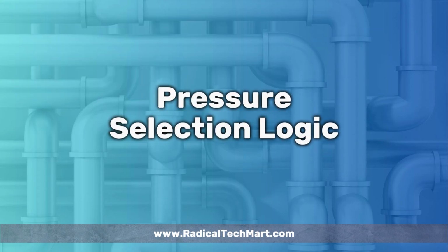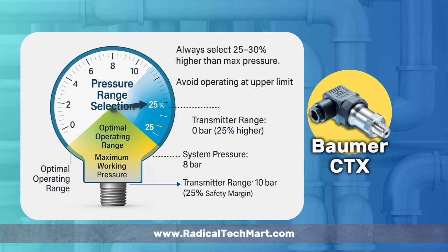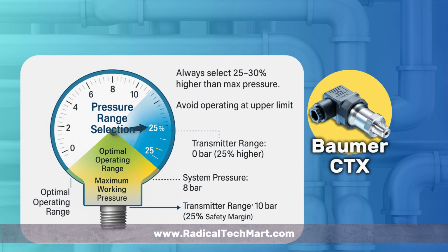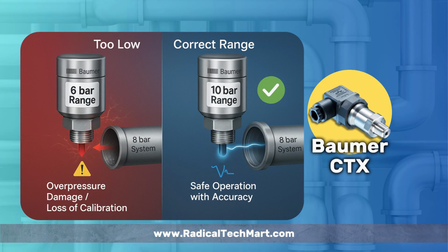Here's a simple selection rule. Always choose a transmitter range that is 25 to 30% higher than your maximum working pressure. For example, if your compressor line works at 8 bar, select a 10 bar range. If your hydraulic system runs at 160 bar, pick a 200 bar transmitter. This ensures accuracy in the operating zone and protects the sensor from pressure spikes. Never select a range that's too low. You'll risk overpressure damage and loss of calibration.